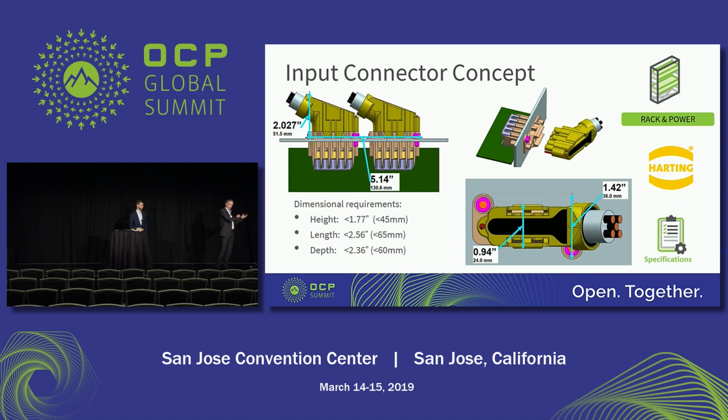And that's true for this design as well. So the connector can withstand it, but it's not really intended to be used like that. It might be difficult fleet-wide to avoid this situation. It might happen, and as a result the resistance of the contact might increase and may cause catastrophic failure over time.